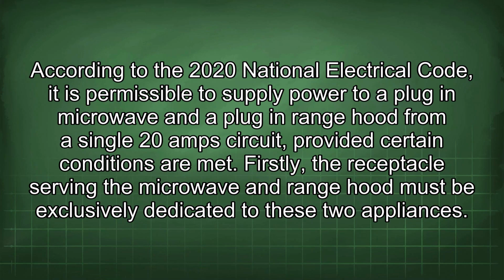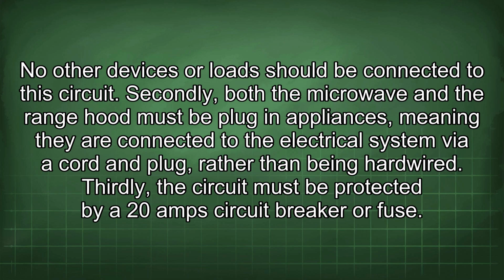According to the 2020 National Electrical Code, it is permissible to supply power to a plug-in microwave and a plug-in range hood from a single 20-amp circuit, provided certain conditions are met. Firstly, the receptacle serving the microwave and range hood must be exclusively dedicated to these two appliances. No other devices or loads should be connected to the circuit.